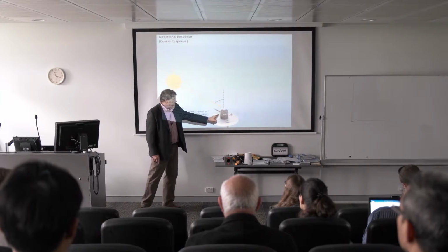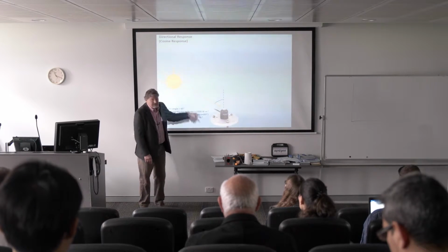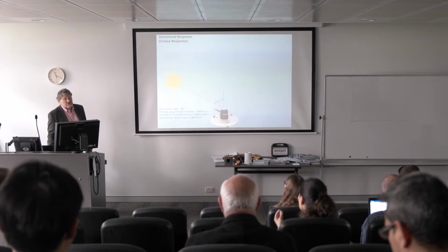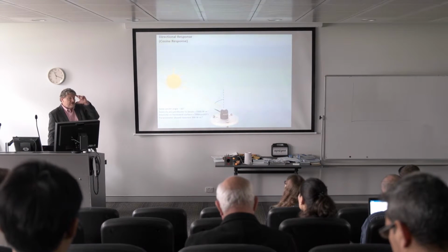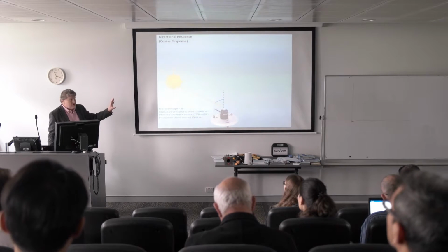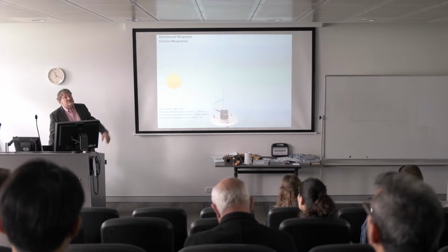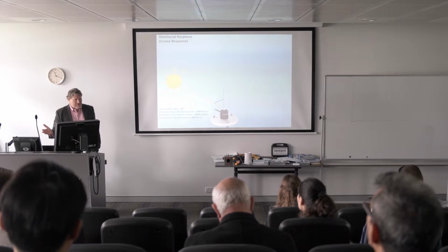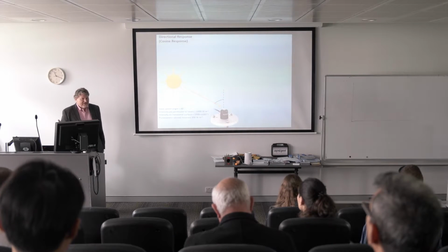Does it really read 500 if it's at that angle? You have to get that correction with the optics of the sensor, and all radiation manufacturers work hard to get cosine correction, at least the ones selling what we call research grade instruments. There's plenty of pyranometers out there that are really cheap, and boy, they do a terrible job of this.